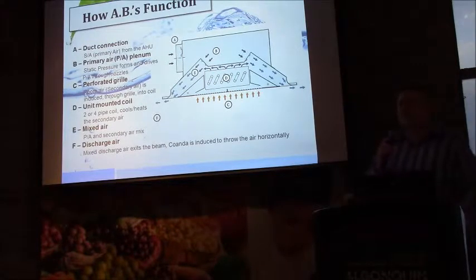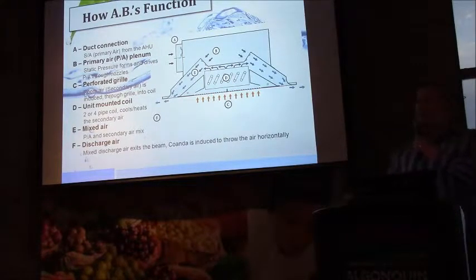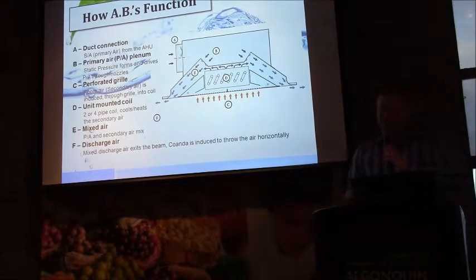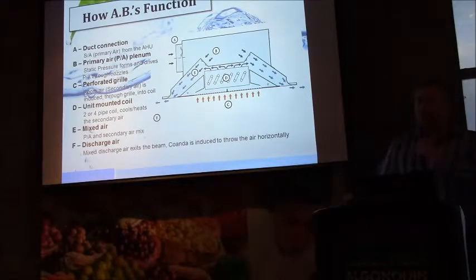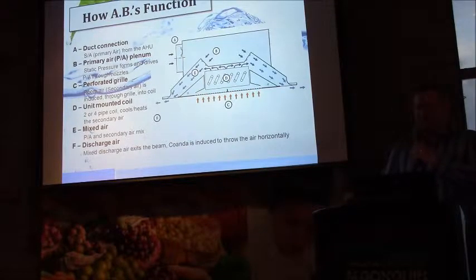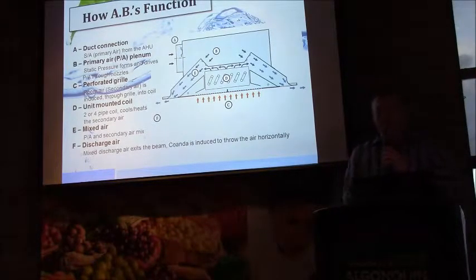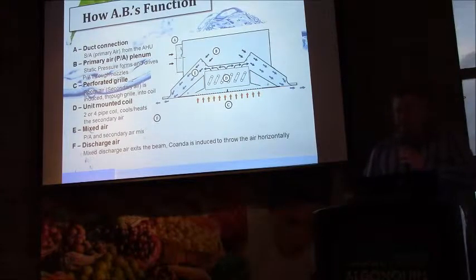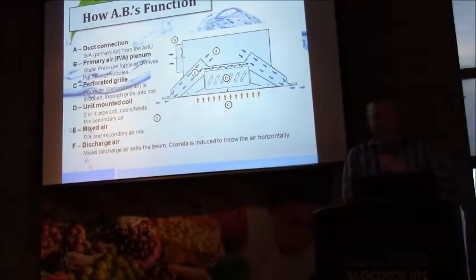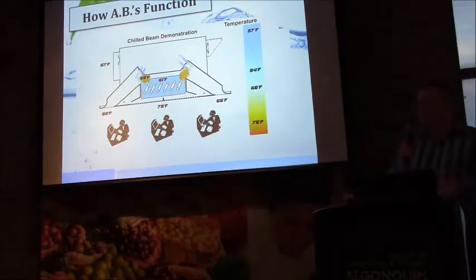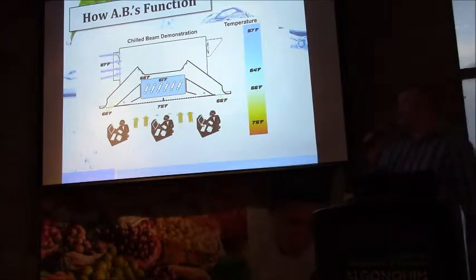The higher the mixing ratio, obviously, the more effect we see for the amount of heat that's extracted from the space at the coil. But fundamentally, those nozzles are chosen to suit the air delivery that's required to offset the latent loads in the space. The coil is held above the dew point of the space and is typically fed with chilled water, of course. And combining the two air streams at E and discharging into the space at F. So I've got a little bit of an animation to kind of show this process in terms of how the air streams mix.